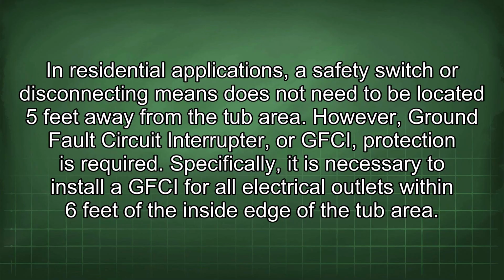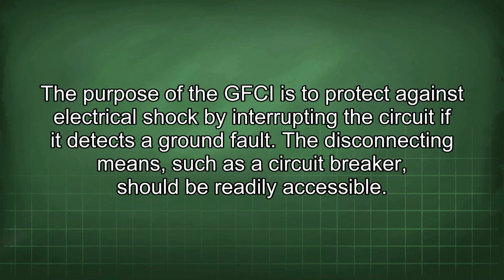In residential applications, a safety switch or disconnecting means does not need to be located 5 feet away from the tub area. However, ground fault circuit interrupter, or GFCI, protection is required. Specifically, it is necessary to install a GFCI for all electrical outlets within 6 feet of the inside edge of the tub area. The purpose of the GFCI is to protect against electrical shock by interrupting the circuit if it detects a ground fault. The disconnecting means, such as a circuit breaker, should be readily accessible.